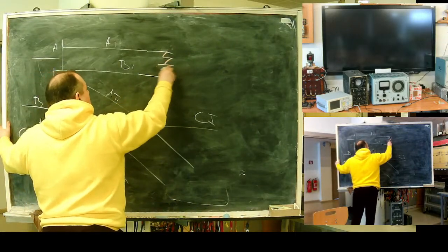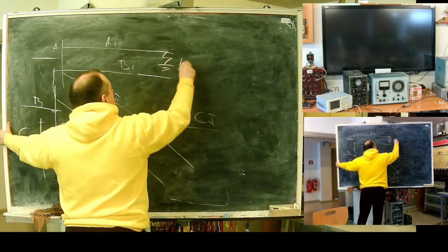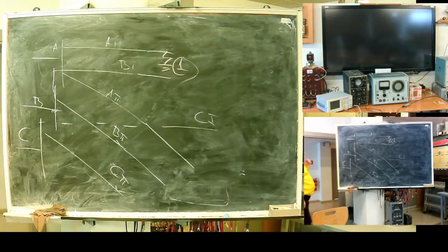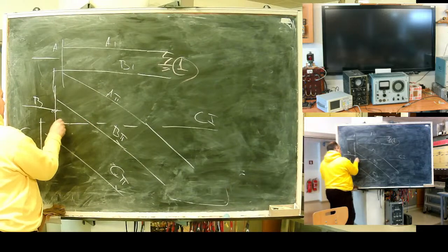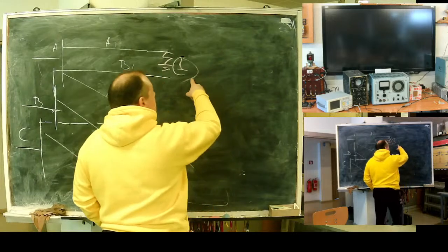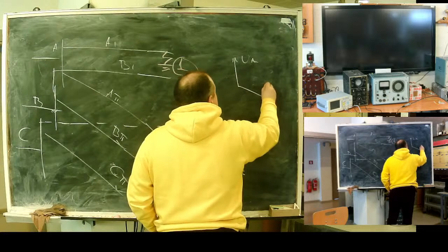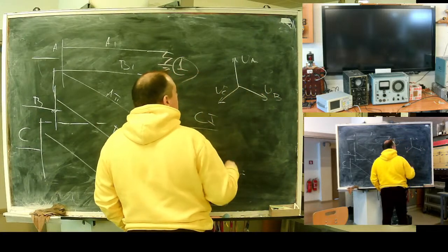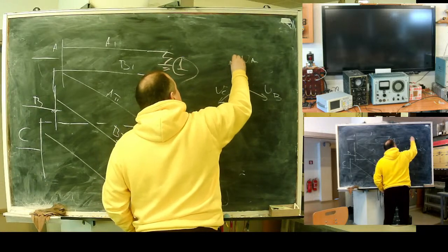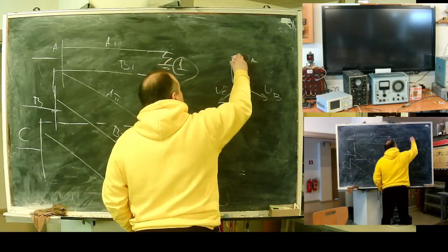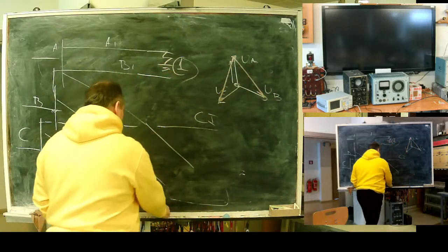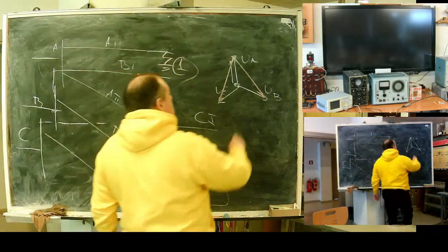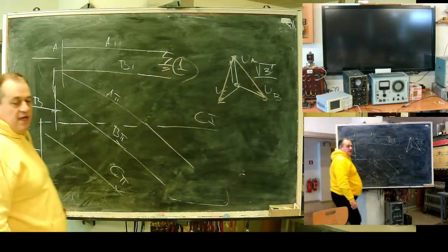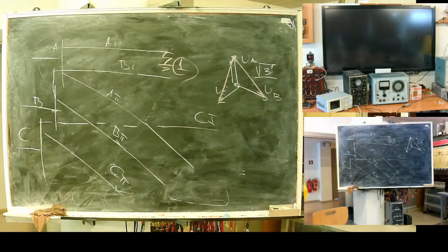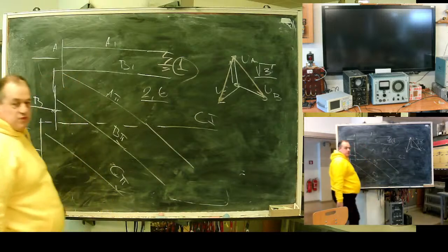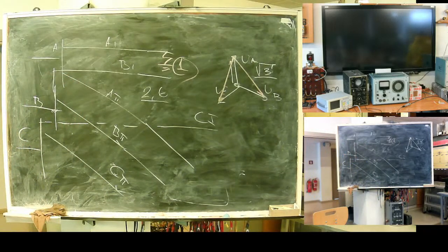And let's say I have an earth fault on my line. What happens? Why am I drawing this diagram? At the moment of fault, the neutral point moves upwards and B and C phase voltages grow up by square root of 3 times. Actually, in the moment of transient, overvoltage, remember this digit, will be 2.6 times voltage for a short time, in the point of transient, 2.6.